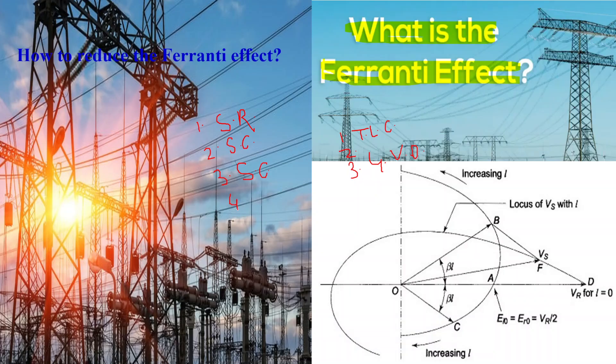Fourth, static VAR compensators. Static VAR compensators are solid-state devices that provide fast and precise reactive power compensation by injecting or absorbing reactive power as required. They help to control voltage levels and minimize voltage fluctuations, including those caused by the Ferranti effect.